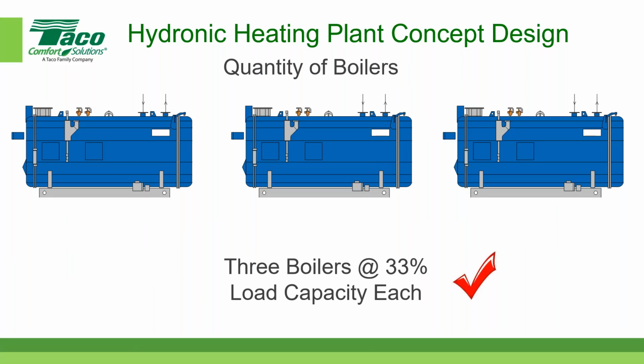The other reason for that is that for 100% capacity, I'd have to run all 3 boilers, but very rarely do I need to have 100% capacity. Generally speaking, it depends on the building configuration, but somewhere between 5 and 25% of the time I would need 100% capacity, which means between 75 and 95% of the time I do not need 100% capacity, which means that I have somewhat built-in redundancy. Any questions about the number of boilers or the combination of boilers?